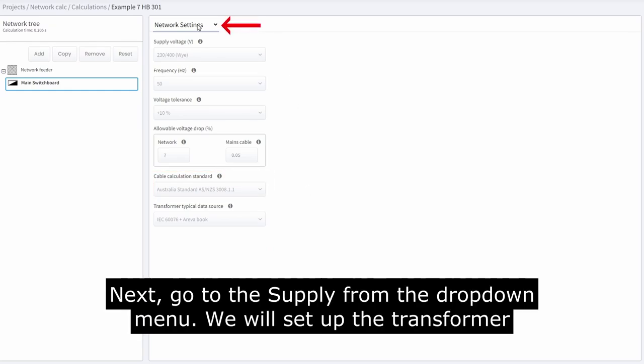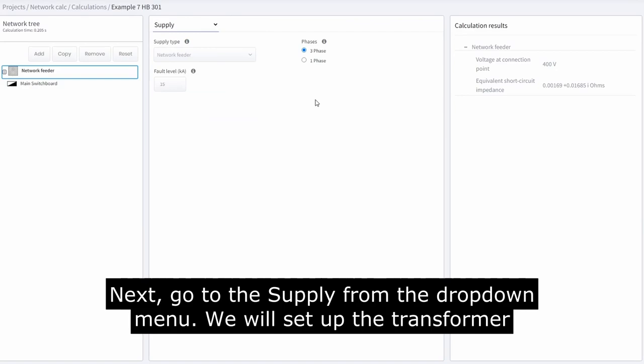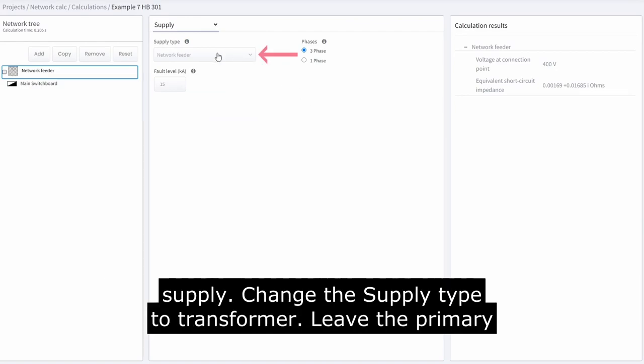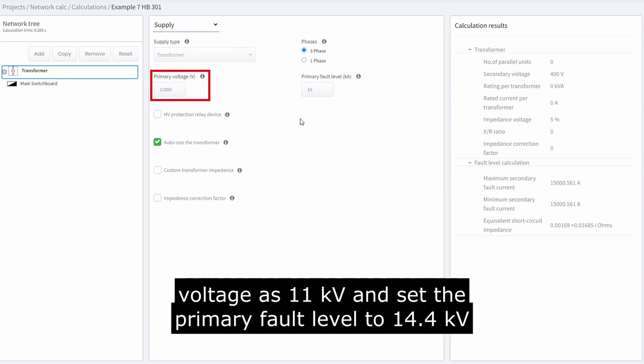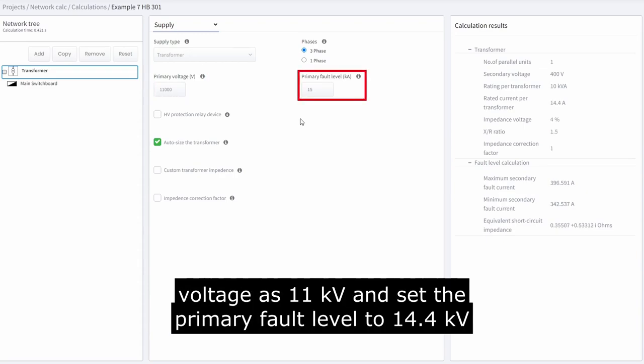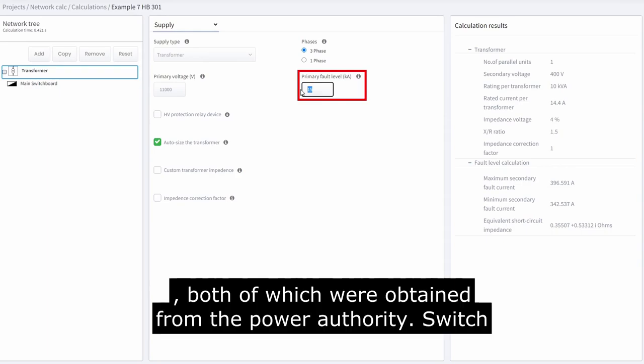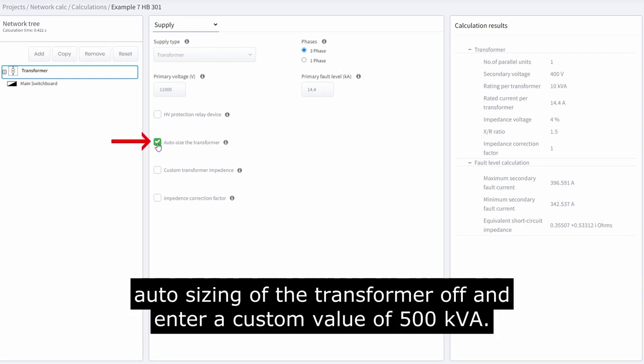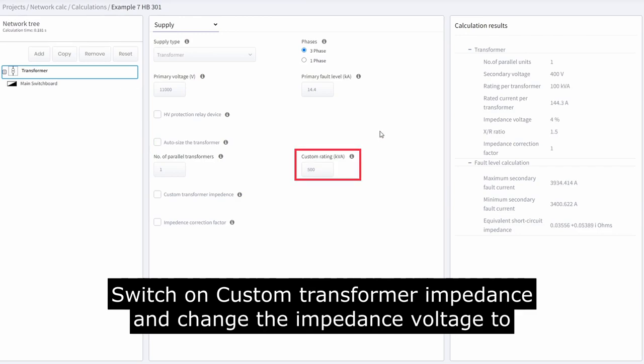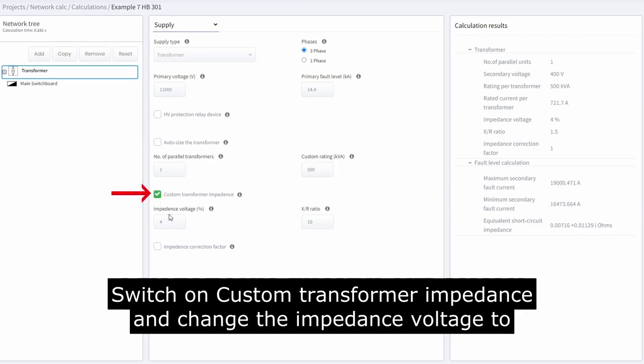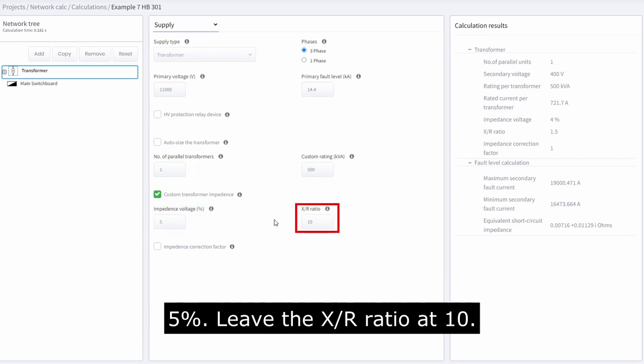Next, go to the supply from the drop-down menu. We will set up the transformer supply. Change the supply type to transformer. Leave the primary voltage as 11 kV and set the primary fault level to 14.4 kA, both obtained from the power authority. Switch auto sizing of the transformer off and enter a custom rating of 500 kVA. Switch on custom transformer impedance and change the impedance voltage to 5%, leaving the XR ratio at 10.